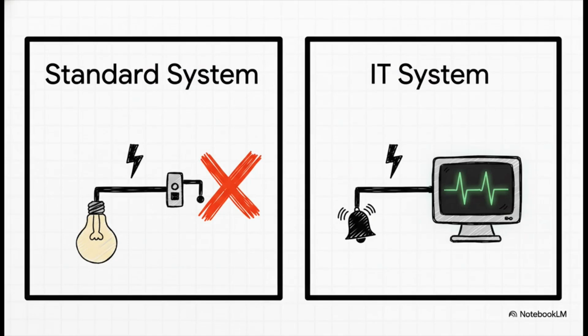Out of these three, I really want you to pay close attention to this one, the IT system. It's specially designed so that if a first fault happens, that first little leak, it doesn't immediately shut everything down. And you can see why that's so important, right? It's exactly why this system is required in places like hospital operating rooms and intensive care units, where losing power even for a split second is just not an option.